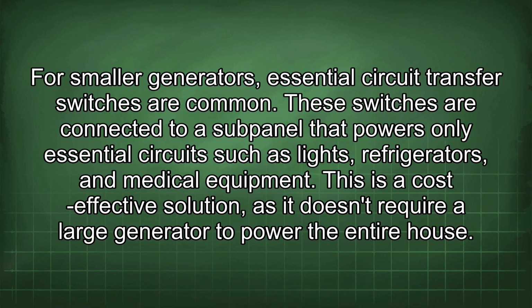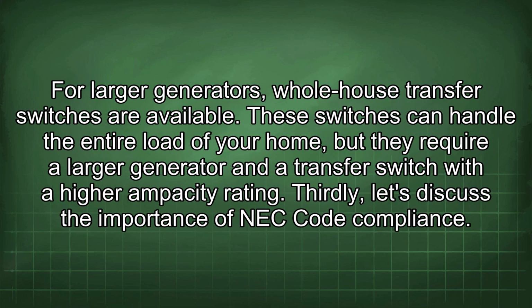For smaller generators, essential circuit transfer switches are common. These switches are connected to a subpanel that powers only essential circuits such as lights, refrigerators, and medical equipment. This is a cost-effective solution, as it doesn't require a large generator to power the entire house. For larger generators, whole house transfer switches are available. These switches can handle the entire load of your home, but they require a larger generator and a transfer switch with a higher ampacity rating.